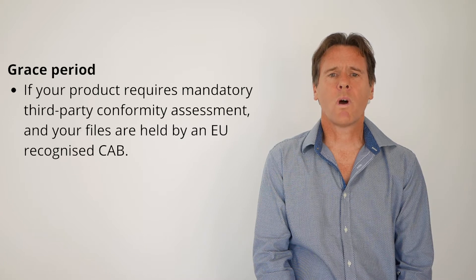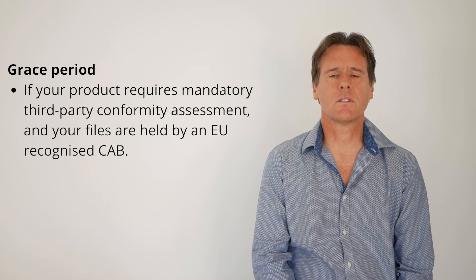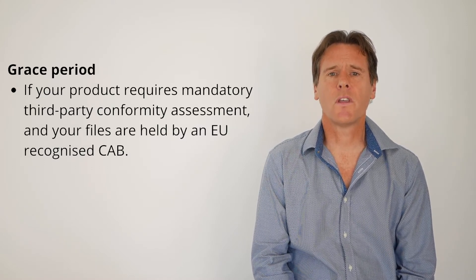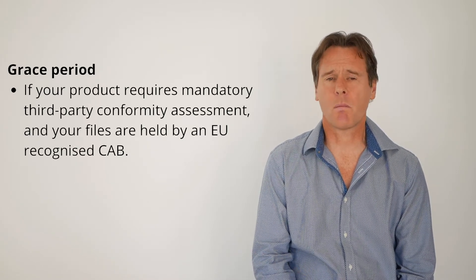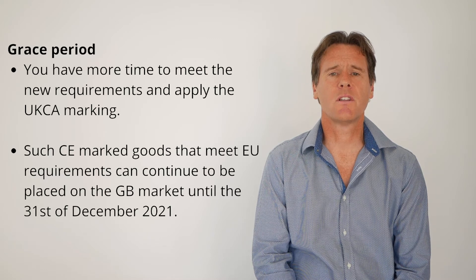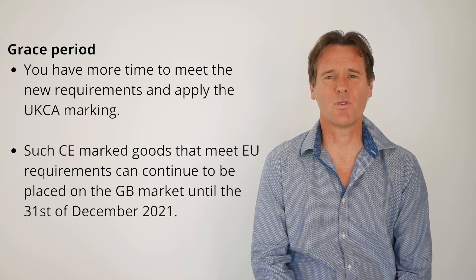Now let's look at the grace period. If your product requires mandatory third-party conformity assessment and provided that the conformity assessment files are held by an EU-recognised conformity assessment body, or can be transferred to one before the 1st of January 2021, you have more time to meet the new requirements and to apply the UKCA marking. The same applies to products that do not require third-party conformity assessment. Such CE-marked products that meet EU requirements can continue to be placed on the GB market until the 31st of December 2021, provided that EU and UK requirements remain the same during that time.